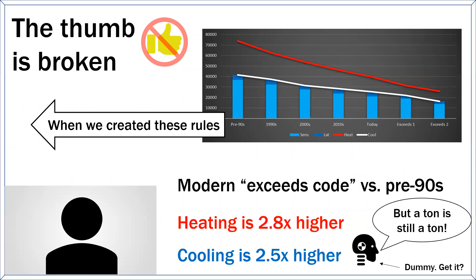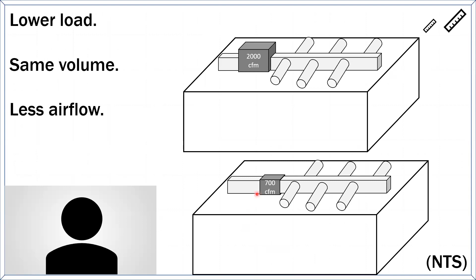And then we talk about ductwork and people are still saying a ton is still a ton. And go watch that. I know the title of this one. It's there's no such thing as a ton. I did it for Jason and you guys a couple of years ago. But this is where you get a lower load. You get the same air volume. You get less airflow. What are some of the negative consequences of that? What is the negative consequence of making the building the same size but the air conditioner a lot smaller?